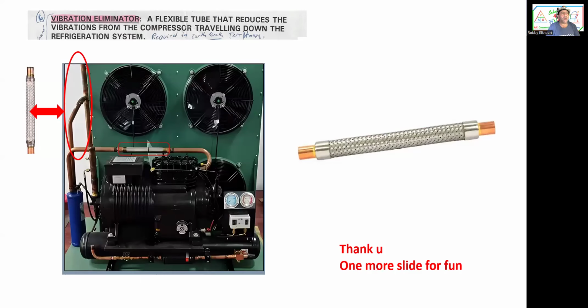One more slide for fun. And we have the vibration eliminator. The eliminator is the last thing. A semi-hermetic compressor comes on, shakes. So we have one here installed in the system on the discharge line. As you can see, going discharge line to oil separator. Huh, interesting. Oh, no, wait, that's the suction line. Whatever that is, that's the suction line. No, whatever that is, that's a vapor. No, it's a discharge line, oil separator to the condenser, correct. And then it goes there. Whoever's going to install this unit, you need to install a vibration eliminator.